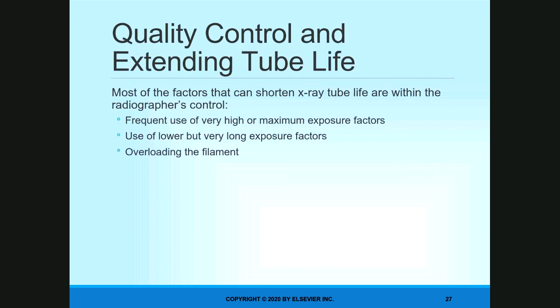The last part of this, they tell you some things that we can do to extend our tube life, because remember, average tube life is about 5 to 7 years, totally dependent on its use. Meaning if you do the preventative maintenance and you take care of the tube and you treat it well and you don't overload it and you try and be mindful of what you're doing, it could very well last you much longer than 7 years. But at the same time, if it's the only machine that you're using and you're using it all day, every day, and you have a ton of patients coming through, it might not even last you 5 years.